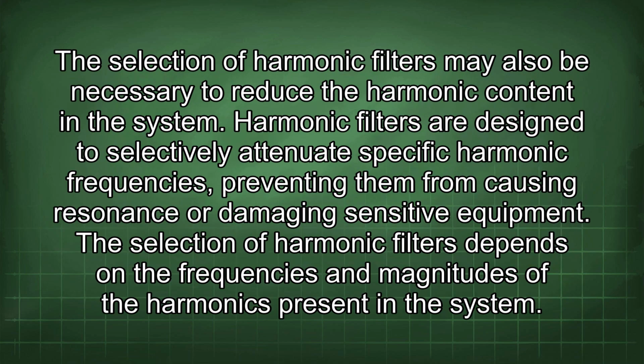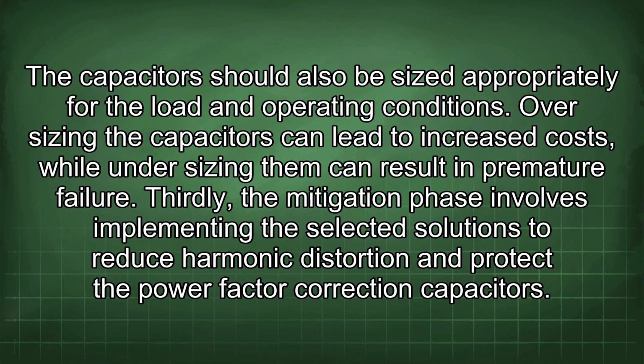The selection of harmonic filters may also be necessary to reduce the harmonic content in the system. Harmonic filters are designed to selectively attenuate specific harmonic frequencies, preventing them from causing resonance or damaging sensitive equipment. The selection of harmonic filters depends on the frequencies and magnitudes of the harmonics present in the system. The capacitors should also be sized appropriately for the load and operating conditions. Oversizing the capacitors can lead to increased costs, while undersizing them can result in premature failure.